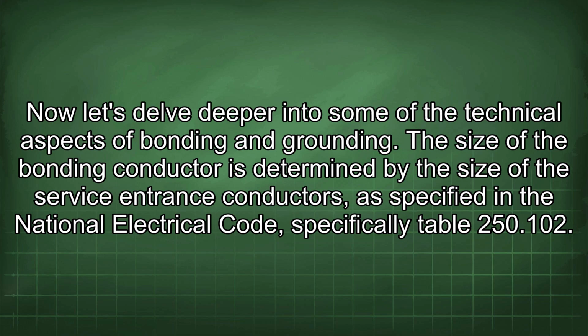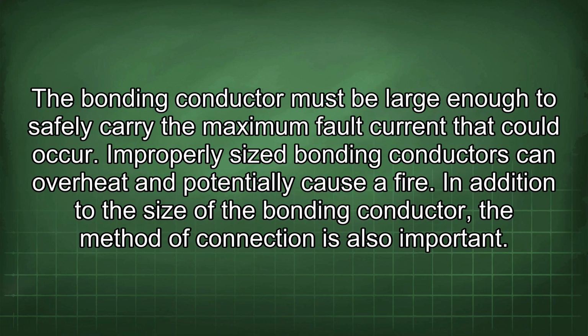The size of the bonding conductor is determined by the size of the service entrance conductors, as specified in the National Electrical Code, specifically Table 250.102. The bonding conductor must be large enough to safely carry the maximum fault current that could occur. Improperly sized bonding conductors can overheat and potentially cause a fire.